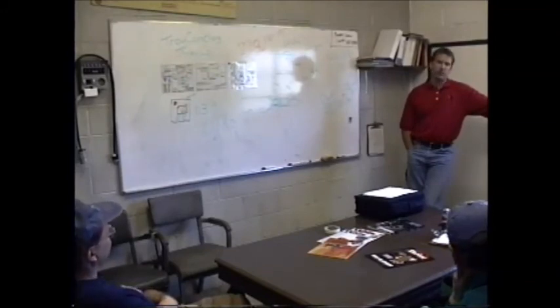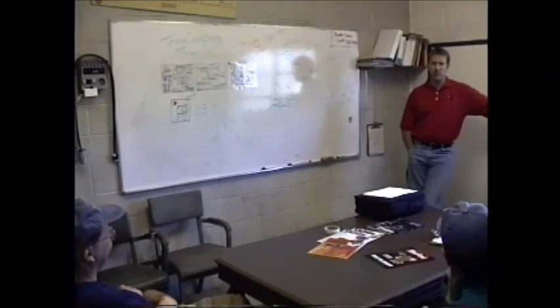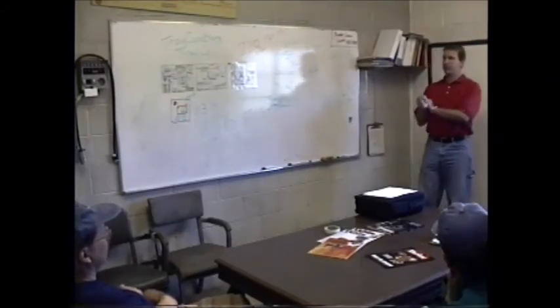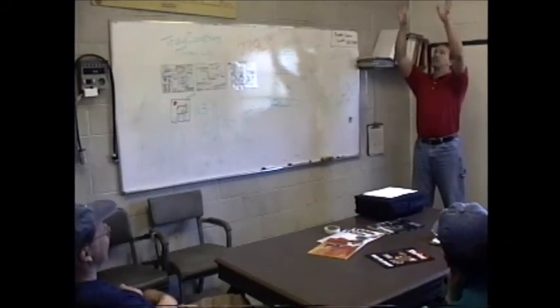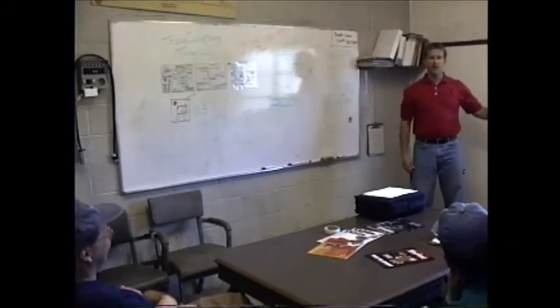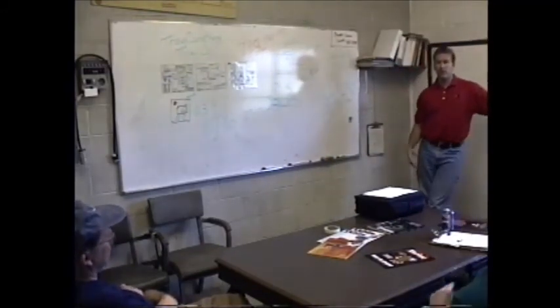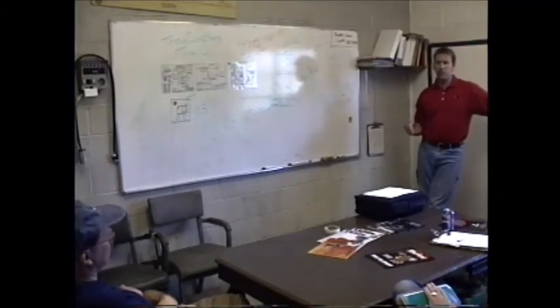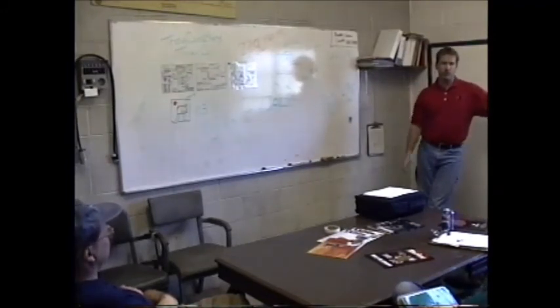I see a lot of people go to a fire and they think the shaving cream type of foam, that really dry foam, is the best foam to use for anything, because that's what they always practice with in their demos or their training. They always make this fluffy shaving cream, and they can't figure out why, as they're shooting it into the fire, the heat just lifts their bubbles up in the air and takes it away, and they don't get anywhere with it. So they need to learn to open the water volume up more and use the propulsion from the air to get it into the fire. But when it comes to actually trying to soak it, I've seen them cover dumpsters.